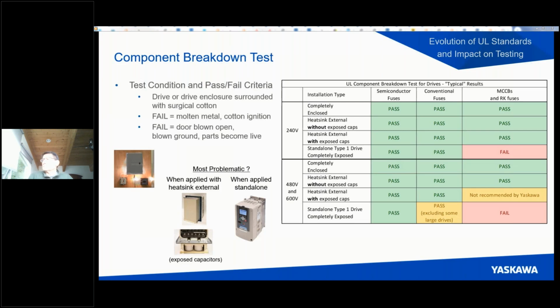Yaskawa does not recommend circuit breakers or RK fuses for protection. That's because we know the test result would not be good. For the new GA800 and GA500, our instructions do not prohibit it, but we still do not recommend. In the future, you are likely to see more conditions of use and instructions, not only from Yaskawa, but also from many drive manufacturers.